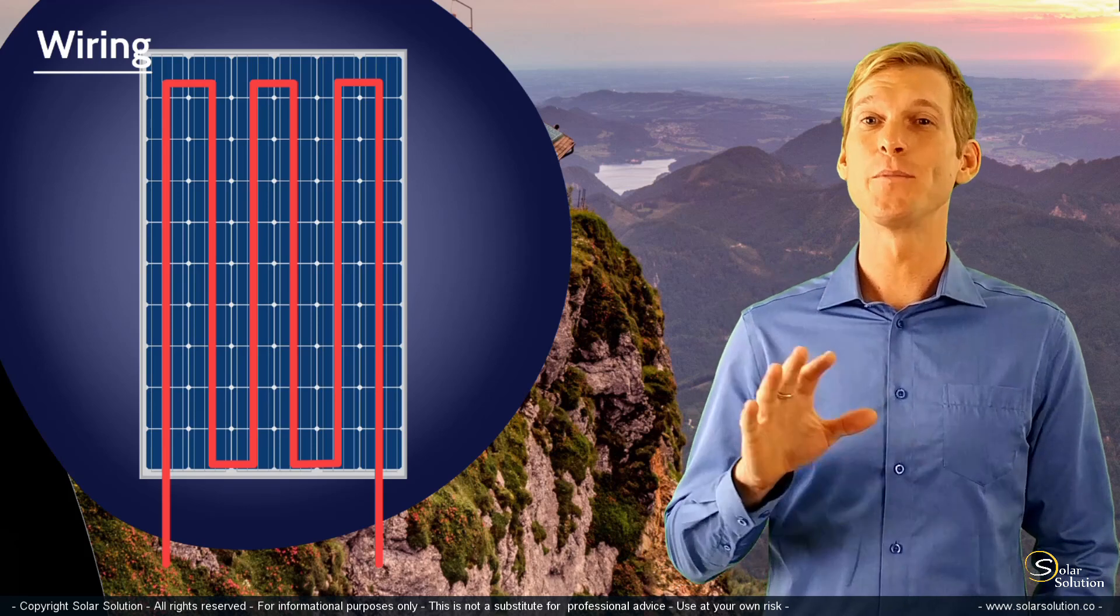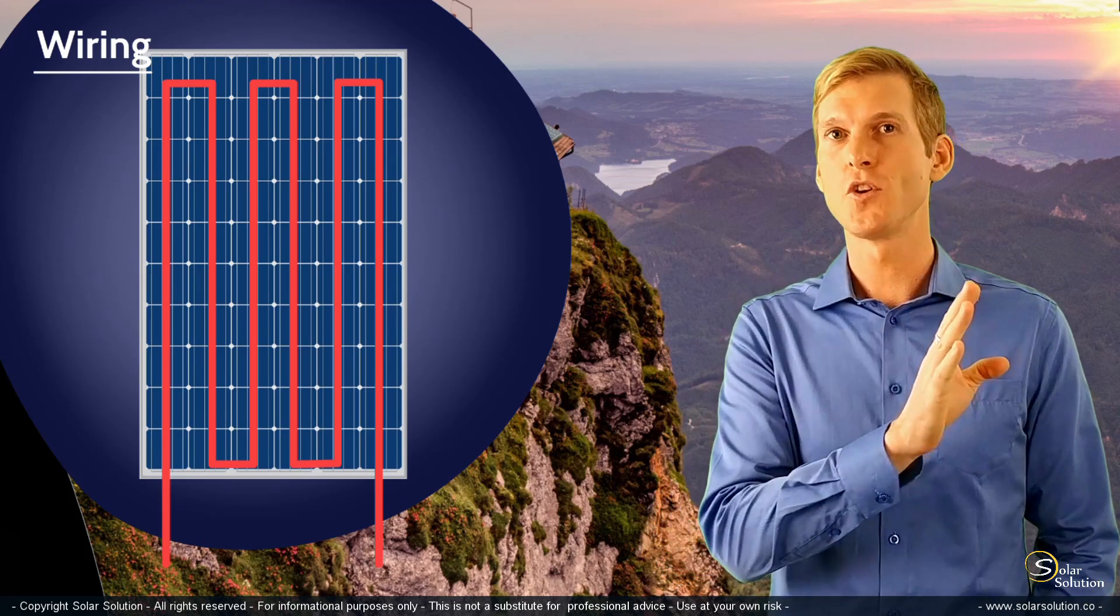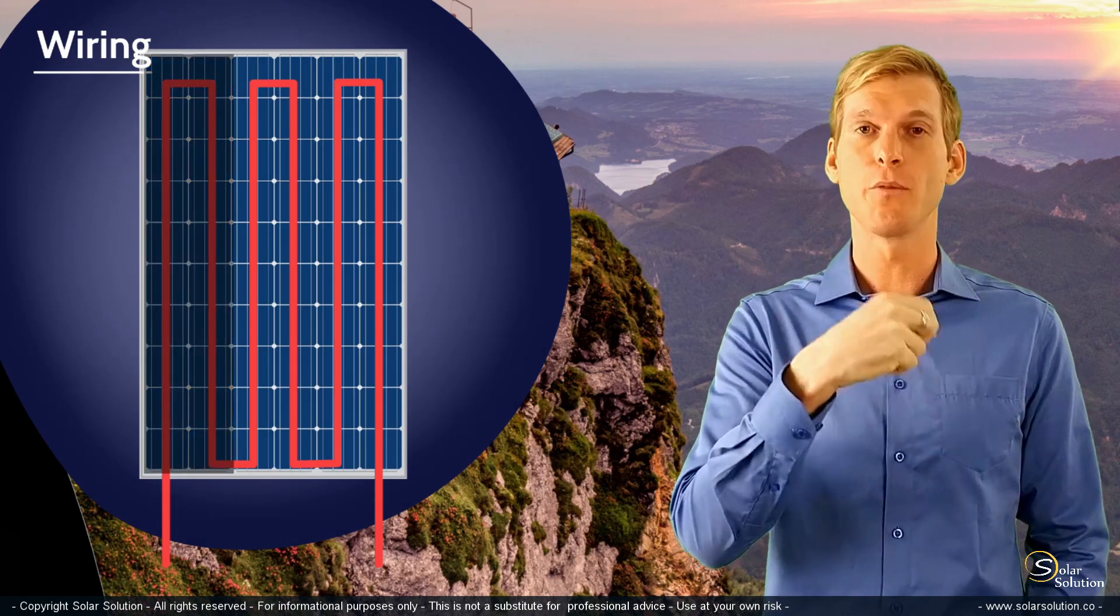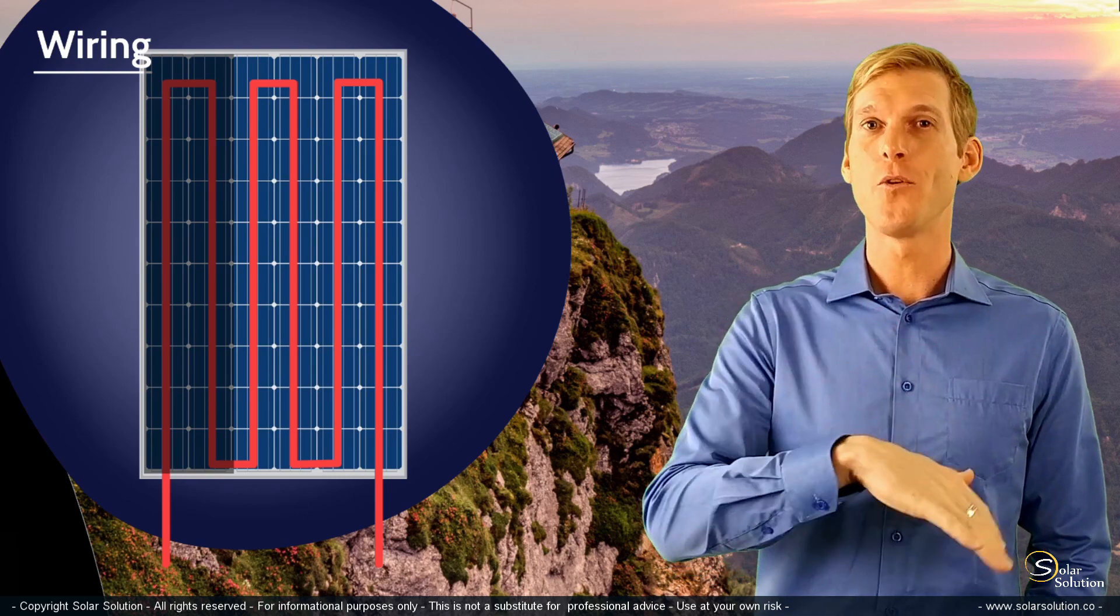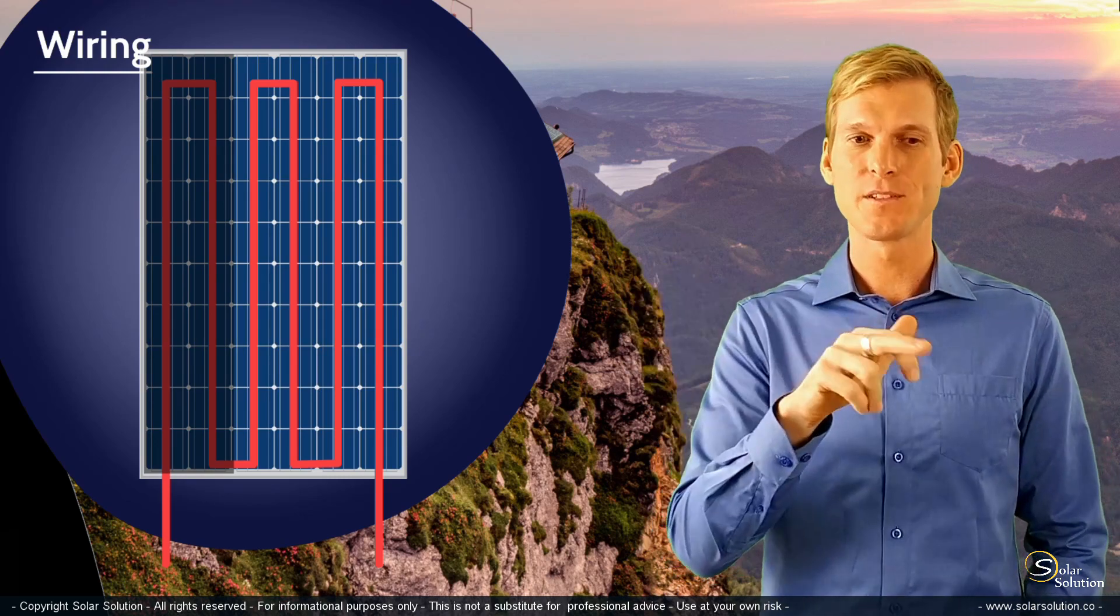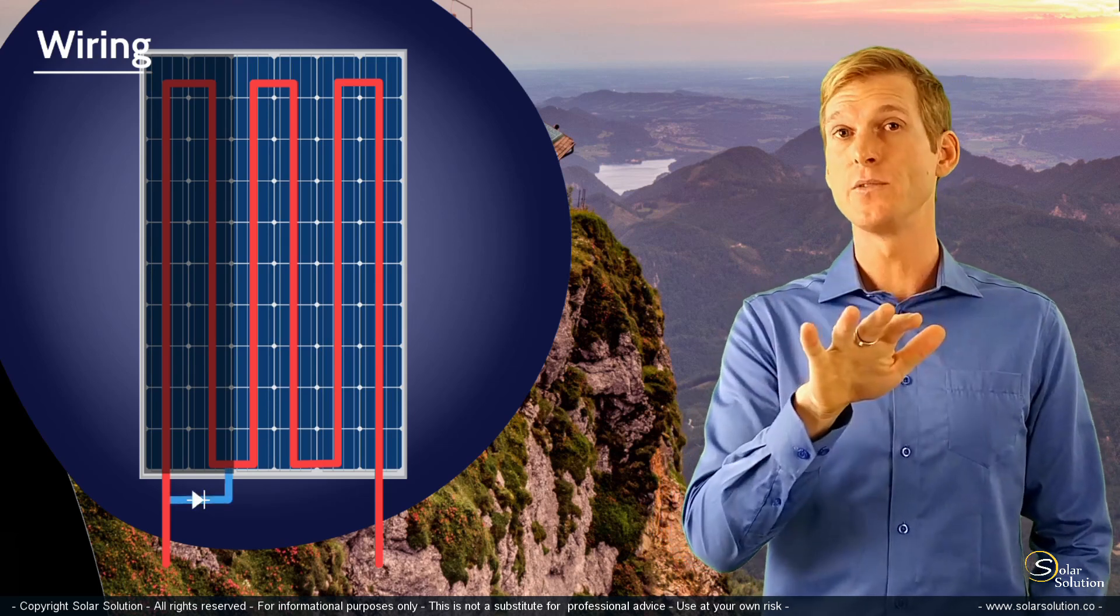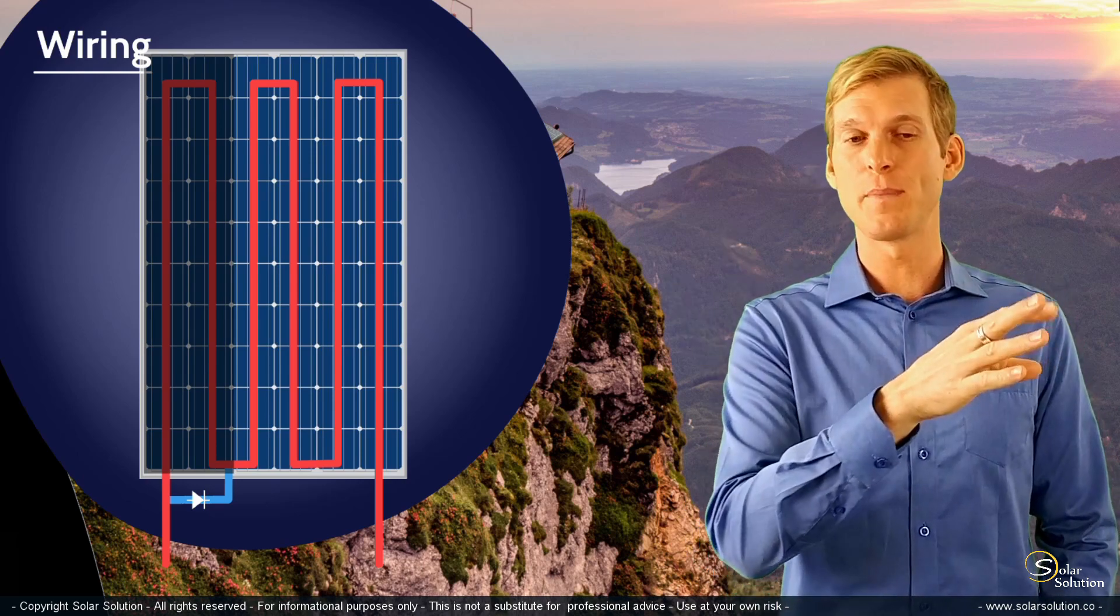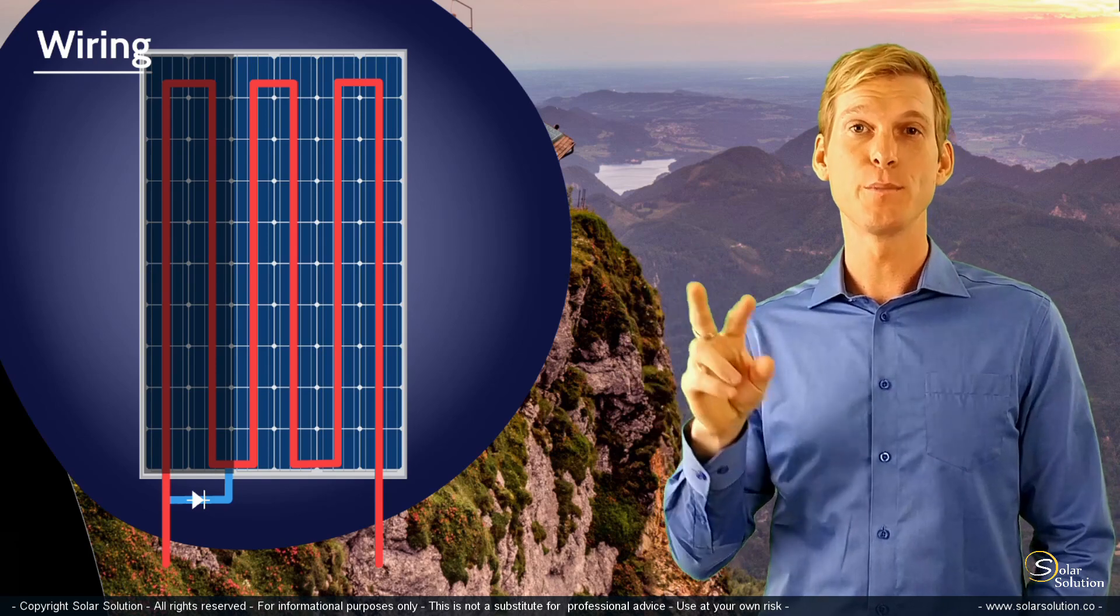Now the bypass diode comes to the rescue. Imagine that the first third of the solar panel is malfunctioning, either due to shade or due to something broken inside the panel. Then, in order to avoid the whole panel from stopping, the bypass diode will provide an alternative path for the electricity to flow. In this situation, the bypass diode will cancel out the first third of the panel and still allow the other two-thirds to perform.